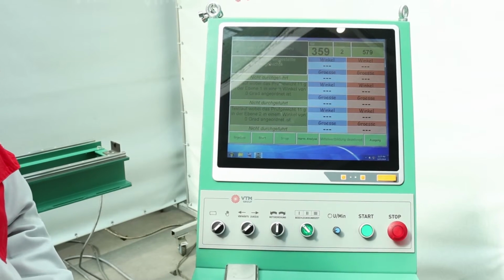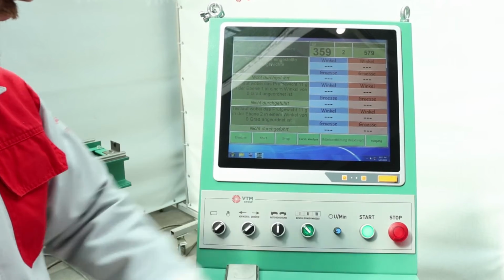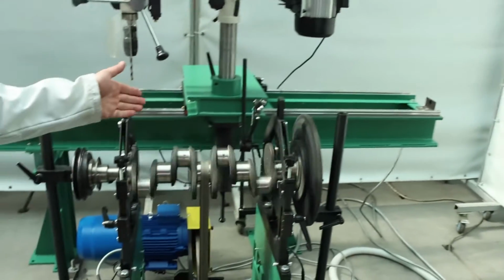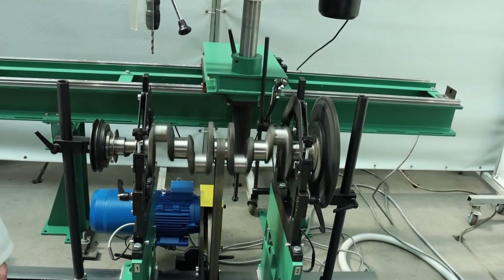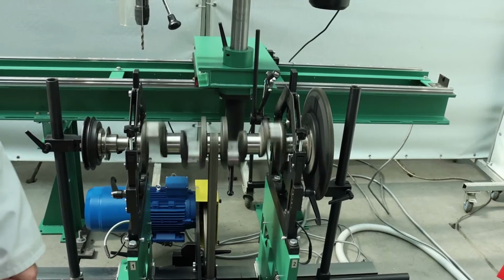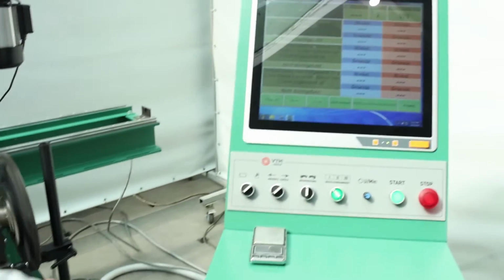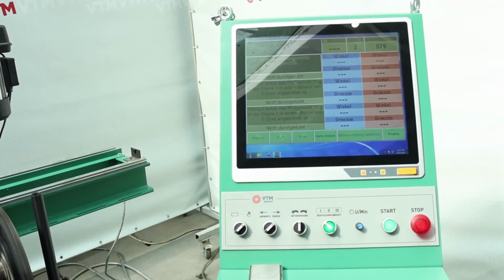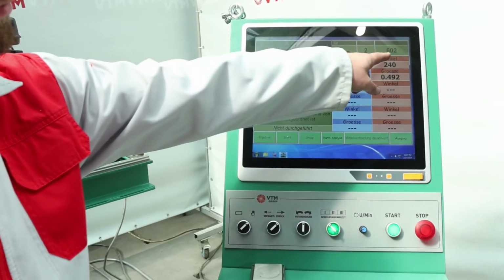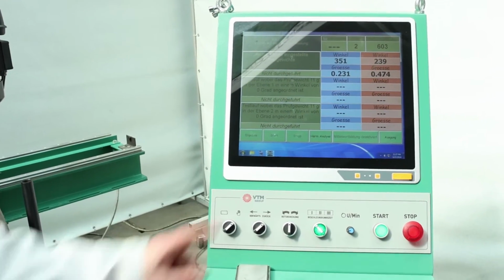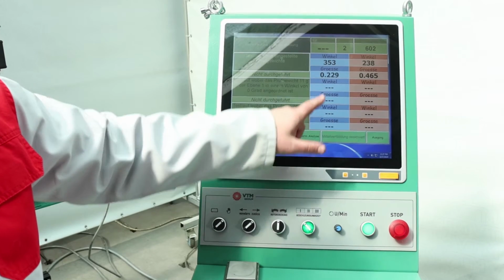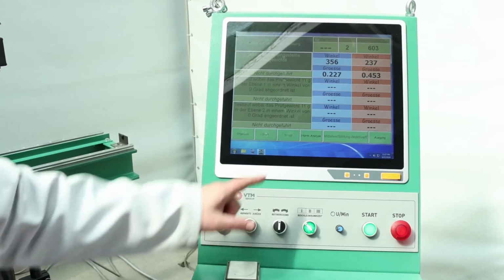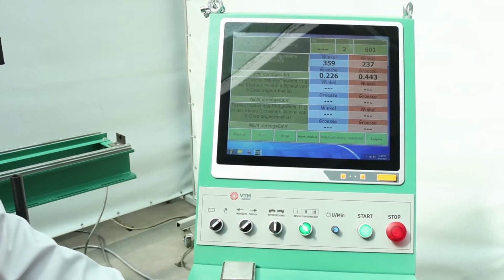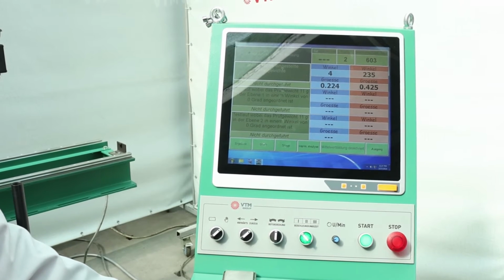Select start without calibration weights, press the start rotation button. The rotor has started to turn. The next step is to press the measurement start button. We see the velocity. You can see the angle of the first and second planes, the value of the first and second planes, and wait for the stop button to activate. The stop button is active.